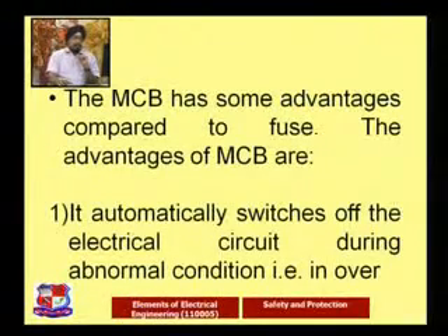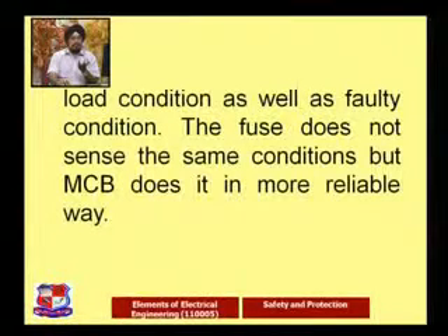What are the advantages? The MCB automatically switches off the electrical circuit or apparatus which we want to protect during an abnormal condition, whether it is an overload condition or faulty conditions. A fuse does not sense, but an MCB can sense. With a fuse, we achieve the protection only when that wire melts. But the MCB can sense before any melting or that process. The MCB plunger can strike and it will go into the off position, and so the MCB is more reliable compared to the fuse.